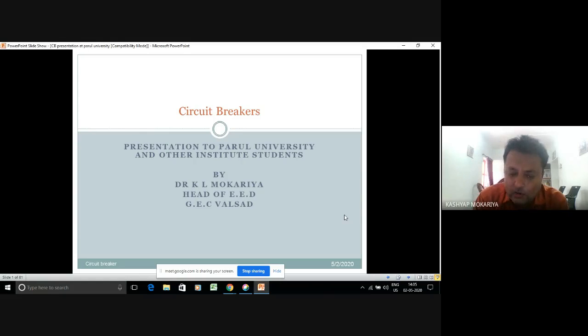Up to 90 kilowatt to 160 kilowatt are LT motors. All these motors are classified as LT motors. 0 to 90 kilowatt LT motors means a 415 volt supply. 90 to 160 kilowatt LT motors are again operated by a 415 volt supply. We were giving them supply and disconnecting the faulty part by means of an air circuit breaker. For HT motors, which have a supply of 6.6 kV, operation is by means of a vacuum circuit breaker.